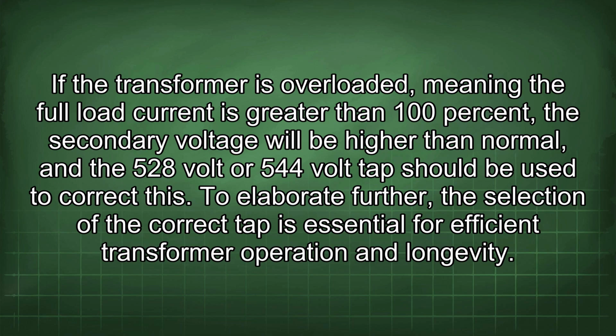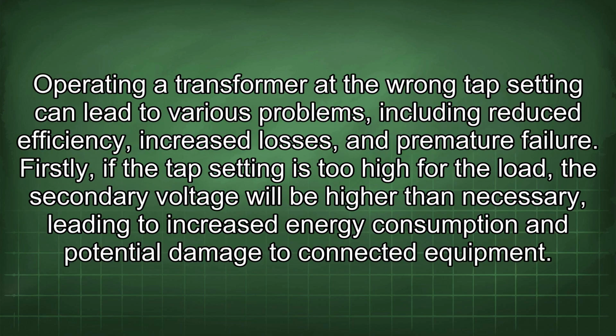To elaborate further, the selection of the correct tap is essential for efficient transformer operation and longevity. Operating a transformer at the wrong tap setting can lead to various problems, including reduced efficiency, increased losses, and premature failure. Firstly, if the tap setting is too high for the load, the secondary voltage will be higher than necessary, leading to increased energy consumption and potential damage to connected equipment.